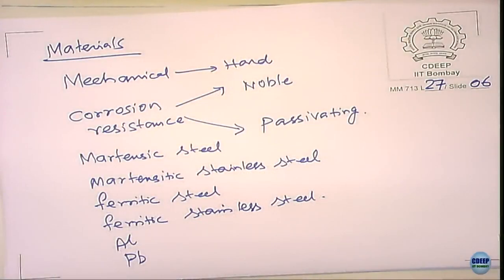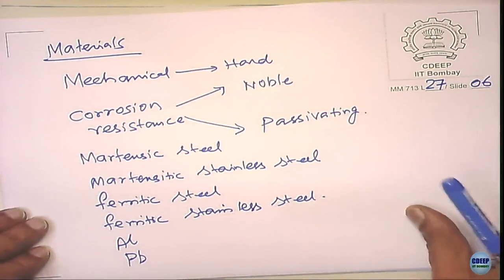Whereas with a high velocity, lead is softer, so it will not even withstand that. So it is not possible to extrapolate given velocities to higher ones, because at higher velocities the mechanism of damage may be different - more mechanical damage dominated than corrosion dominated. At low velocities, what is the dominating mechanism? Low velocities is corrosion. At higher velocities, the dominating mechanism will be mechanical factor. So it is not possible to just make extrapolations the way you want.